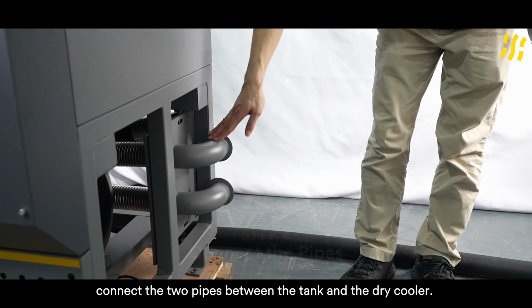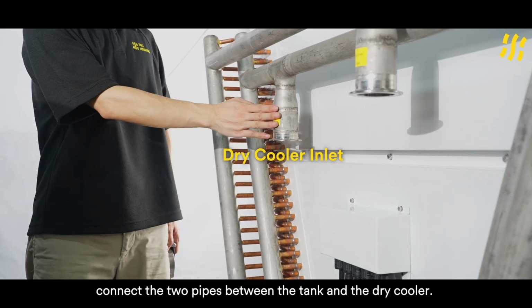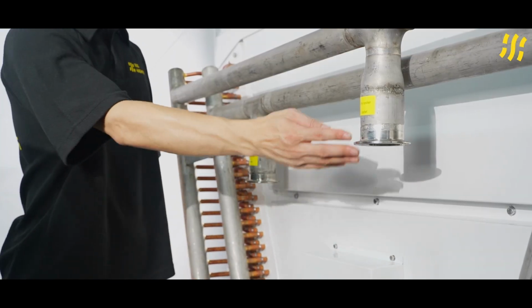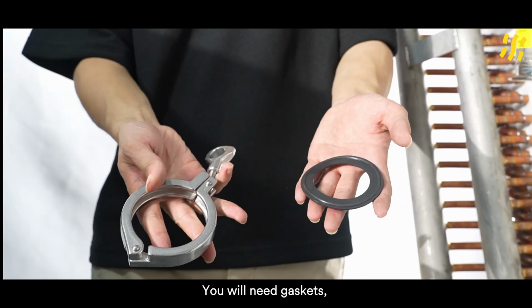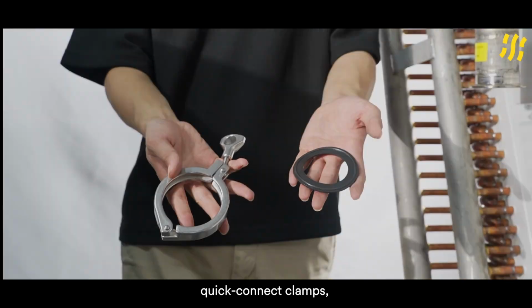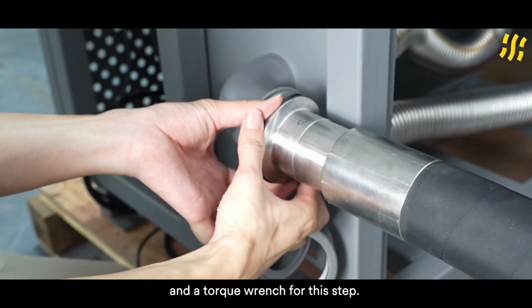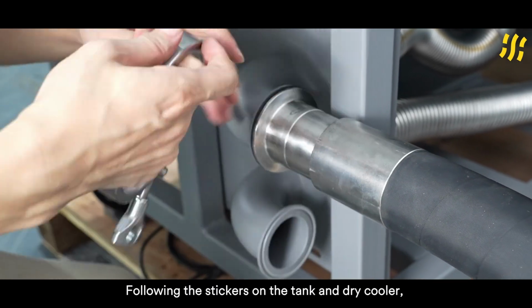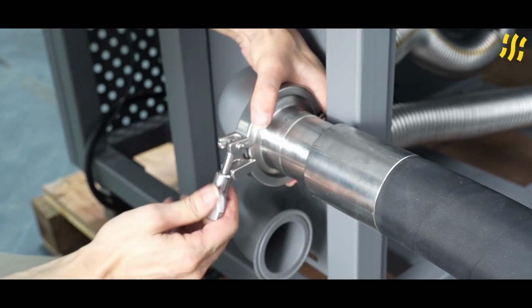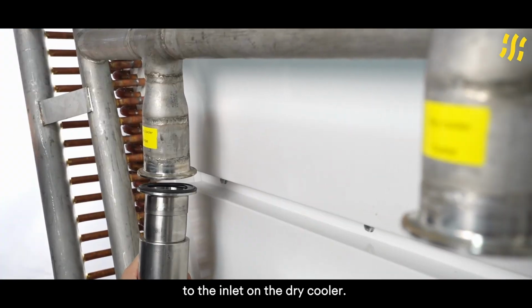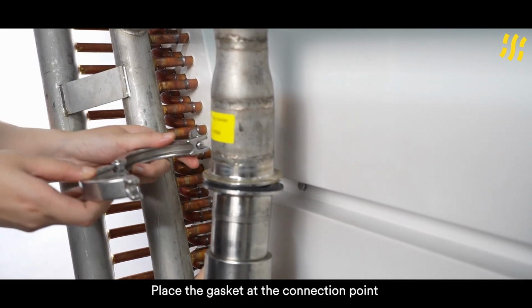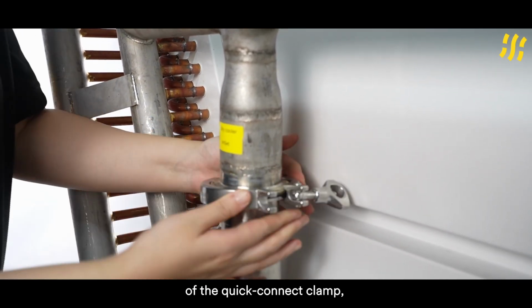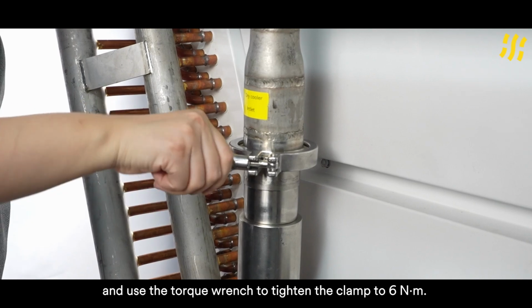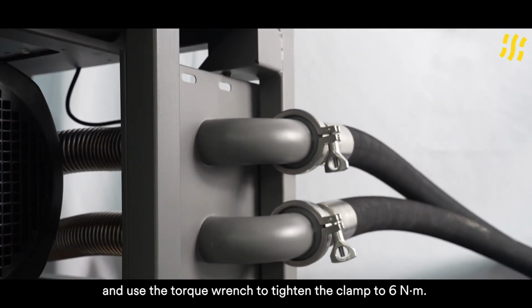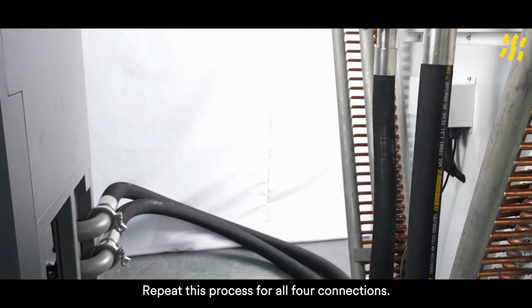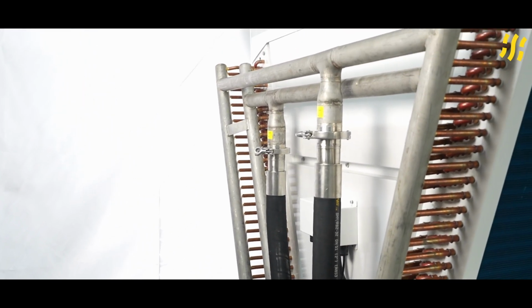First, connect the two pipes between the tank and the dry cooler. You will need gaskets, quick connect clamps, and a torque wrench for this step. Following the stickers on the tank and dry cooler, connect the outlet on the tank to the inlet on the dry cooler. Place the gasket at the connection point of the quick connect clamp and use the torque wrench to tighten the clamp to 6 Nm. Repeat this process for all 4 connections.